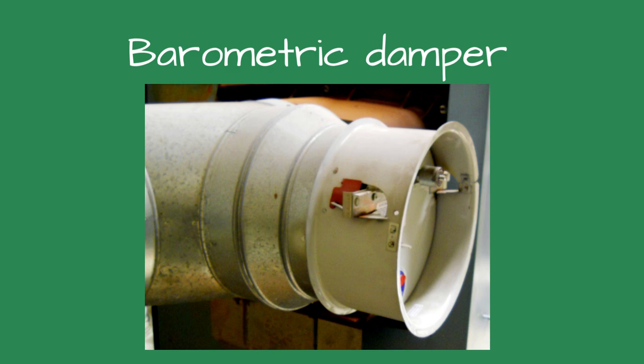Why didn't I see it before, I wondered. The contractor installed a reducer in the T and used a smaller barometric damper. The damper was wide open and too small.